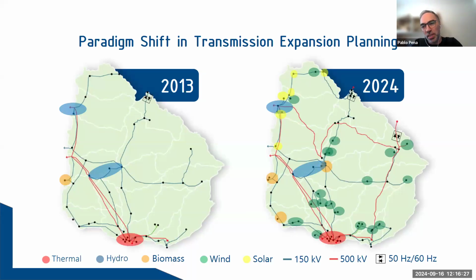Historically, power generation in our network, as Virginia said, was concentrated at very few nodes, and the grid was minimally meshed, resulting in well-defined flow patterns, either thermal or hydraulic, coupled with winter or summer peak demands. This simplicity allowed us to analyze and design the transmission network based on a small pool of worst-case scenarios, which is typical in transmission system analysis.